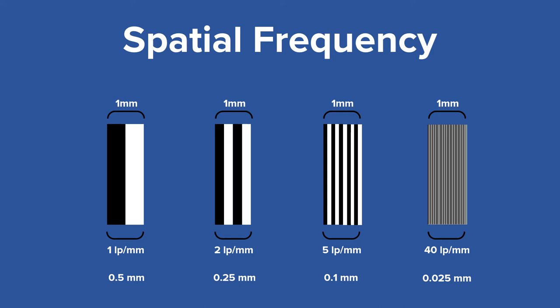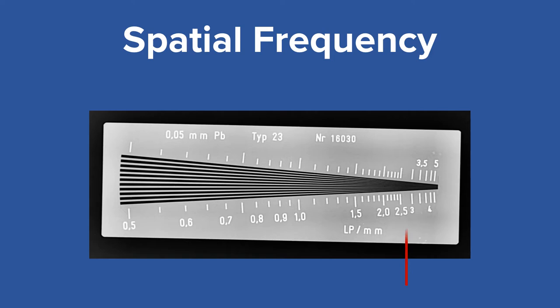What's the smallest line pair you can see? I can see about 2.75 line pairs per millimeter. Unfortunately, with this image, I can't see all the way down to five line pairs per millimeter.